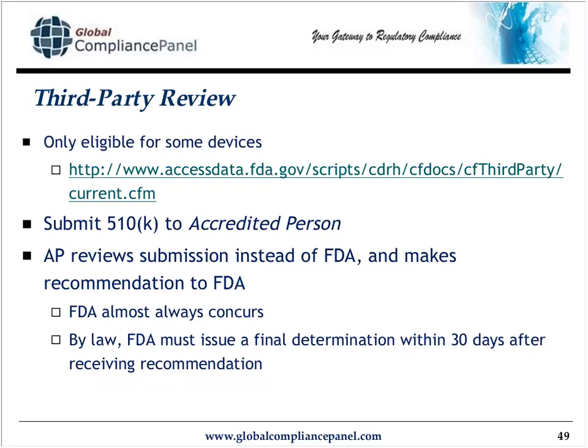I mentioned earlier, very briefly, the concept of the third-party review. It's not eligible for every single device out there, but it is eligible for quite a few of them. In this case, when I have my 510K, I'm not going to submit it to FDA. I'm going to submit it to what's called an accredited person. And the accredited person reviews the submission instead of the FDA, because the FDA has licensed them, has authorized them to do this. And they make their recommendation to FDA.